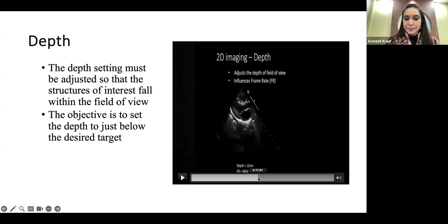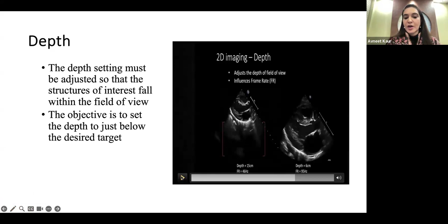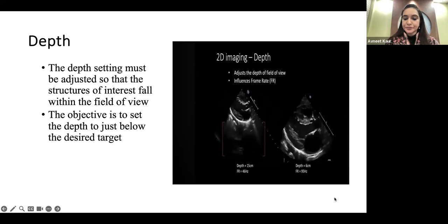So if you can see, I kept my depth at 15 and my frame rate was 46. When I reduced my depth, you can see my image has come to the center, and my frame rate has improved, which has led to better image resolution. So that's how depth is one of the very important parameters to improve the resolution and the quality of our image.